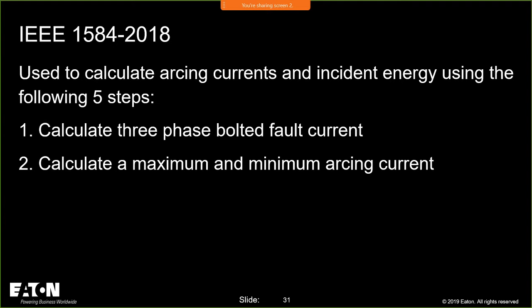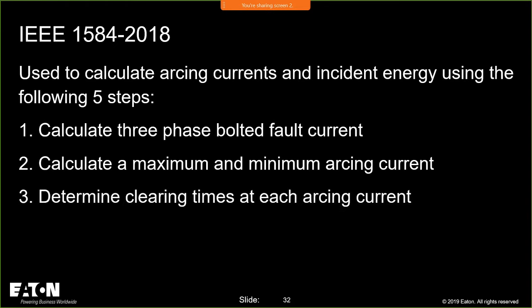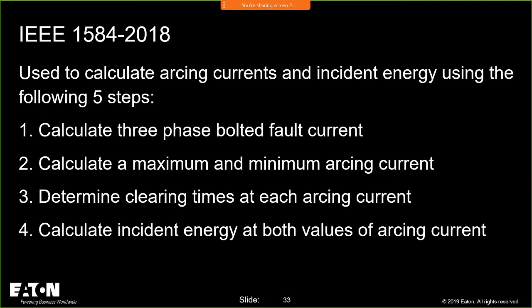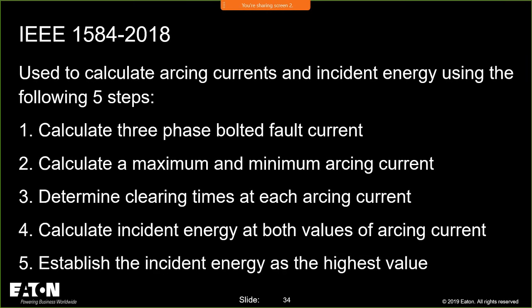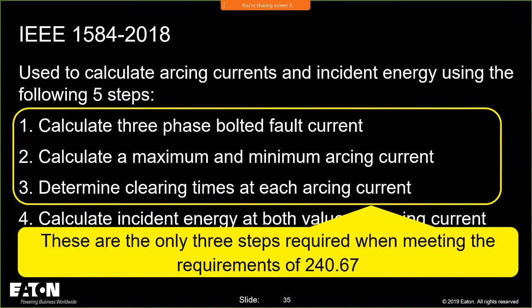The second thing we do is we plug that data plus other data with regard to the configuration of the bus, the distance between electrodes and all that good stuff, and we get a minimum and maximum arcing current. And then we determine the clearing times for both of those. And then with those clearing times and those arcing currents, we calculate an incident energy value at both of those arcing currents, and we pick the highest of the two. So that's the basic process 1584 outlines to calculate incident energies, and those are the numbers that we use for electrical workers to dress. But for 240.67, we only need the first 3 pieces of the pie, or puzzle, whatever you want to call it. So those are the first 3 pieces that we need.